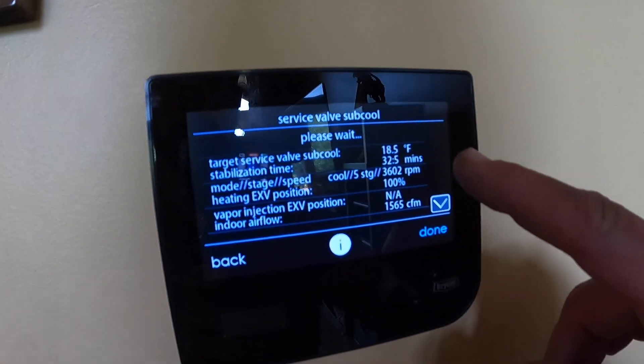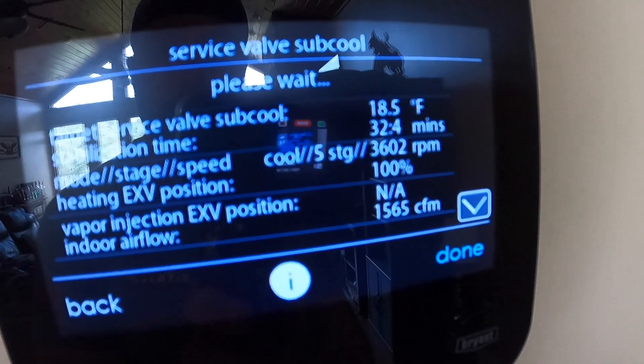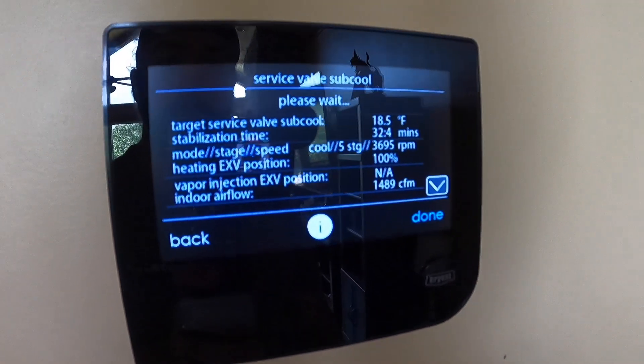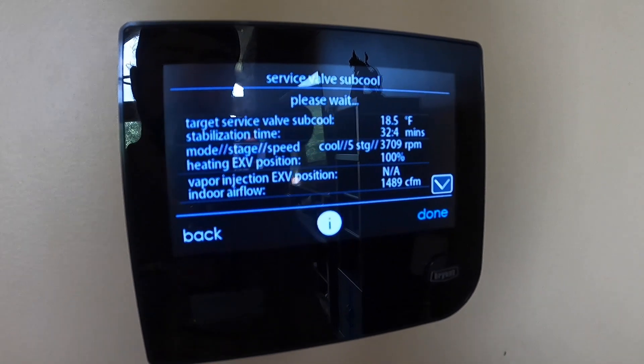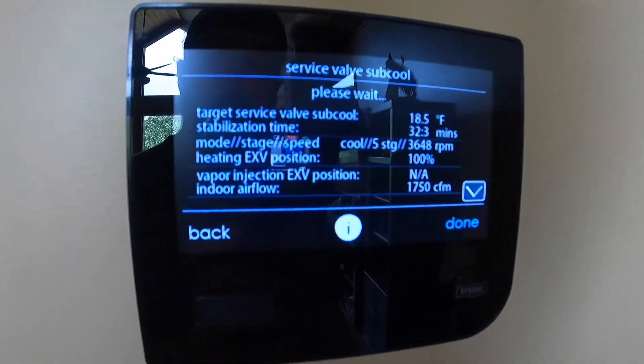This will get started and it'll tell you — we've got 32.4 minutes to go. So we're going to let this run through the stabilization time, and then we're going to go out and check the subcool for 18.5 degrees. I'll follow back up when we get done with that.